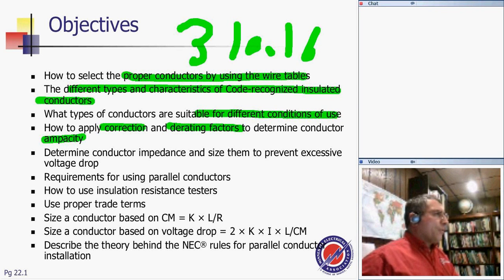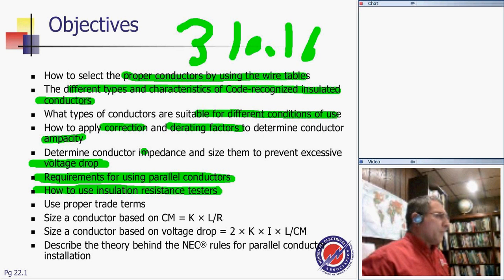I'm going to jump into 310.16 and a couple of other tables. Another thing, guys, is sizing based on voltage drop. How do you size a conductor based on voltage drop? Because we size based on current, we size based on temperature, we size based on how many are in one conduit. We also have to size based on voltage drop and distance: how far you can run a cable and still get the voltage out of it. Using parallel conductors, we have listed requirements, and I'm sure a lot of you probably know that. Also, how to use an insulation resistance tester to measure a circuit and make sure that you don't have a ground fault or a short circuit between the three phases.